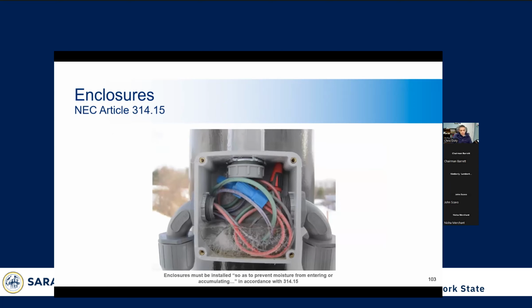This is kind of an interesting situation. We have an outdoor rated enclosure that was just not installed properly. You can't really see it in this picture, but the conduit entry point isn't properly sealed at the top of the enclosure right here. And so water got in, and luckily the wire nuts were such that they were not down in the pool of water.